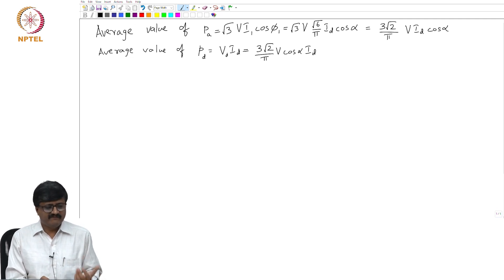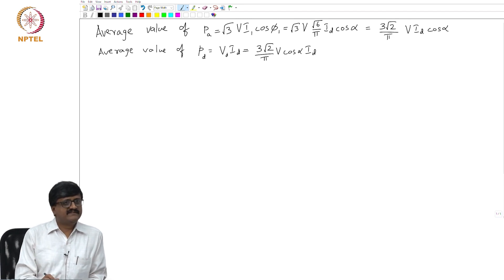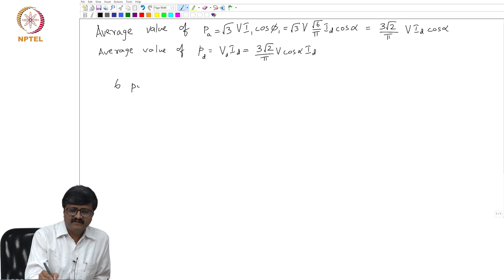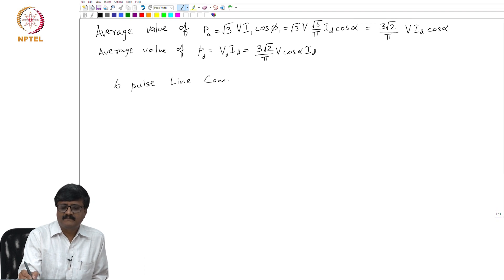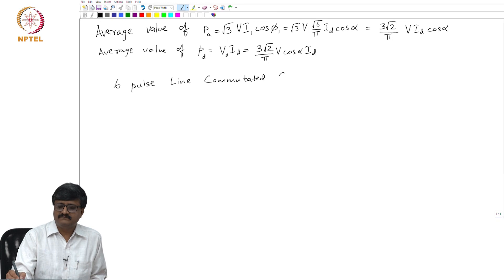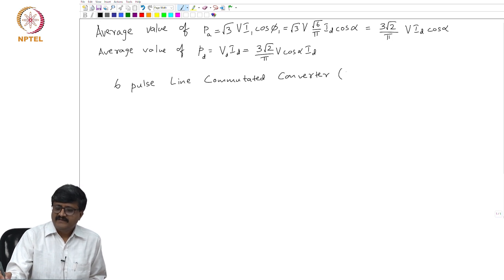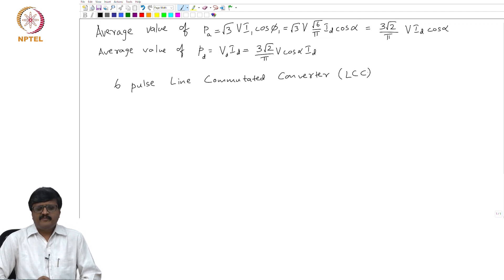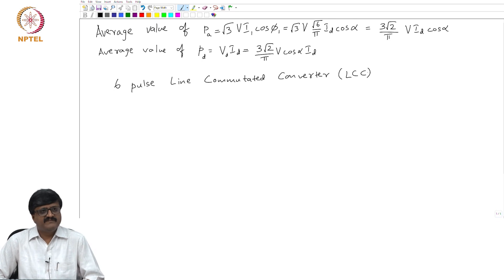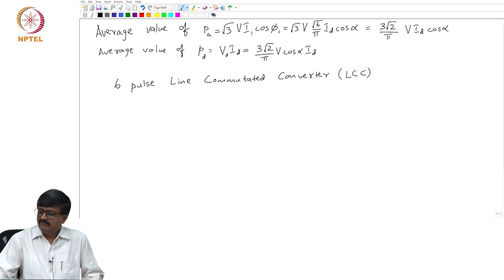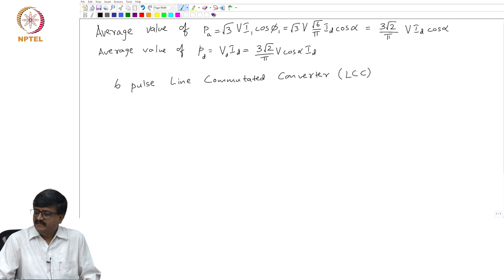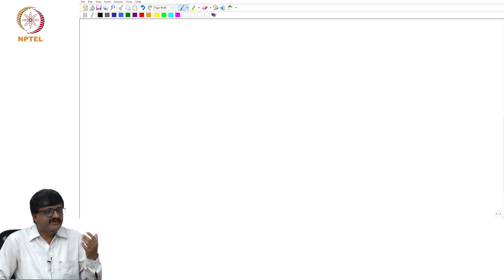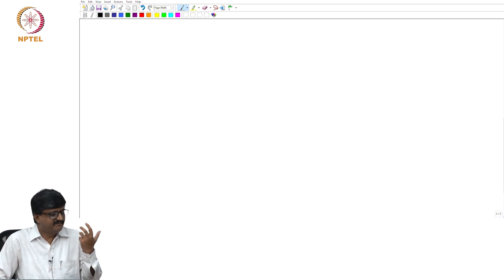The converter we have considered so far is a 6-pulse line commutated converter, with the AC side represented by just a voltage source. This line commutated converter is abbreviated as LCC. We analyzed a 6-pulse line commutated converter with the simplification that the inductance on the AC side is zero. That simplification was just for convenience — in reality there will be inductance on the AC side, because the AC side cannot be represented by a voltage source alone. This voltage source is the EMF induced in a transformer, and a transformer invariably has leakage inductance.